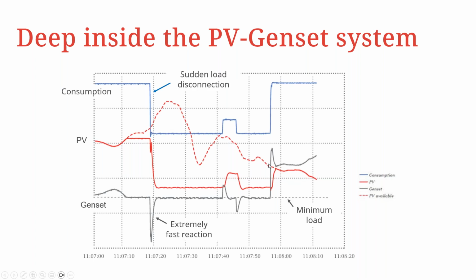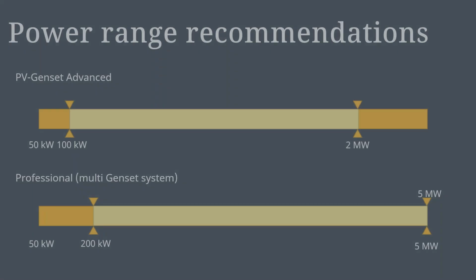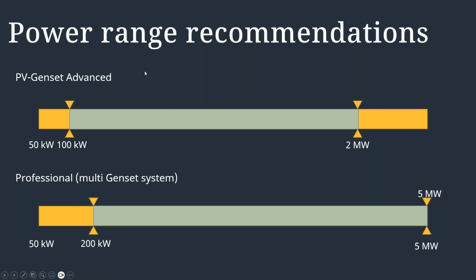Good. Going forward, let's give a power range recommendation. A sweet spot for applying the PV Genset Advanced is usually between 100 kilowatts and 2 megawatts. You might want to go below or above that, but then we're looking at the economy of scale and the cost of components. So the sweet spot is recommended to fall between 100 kilowatts and 2 megawatts. Then for the Professional PV genset solution, comprising multiple genset systems, the sweet spot is recommended to be between 200 kilowatts and 5 megawatts. No harm going slightly below this, of course.